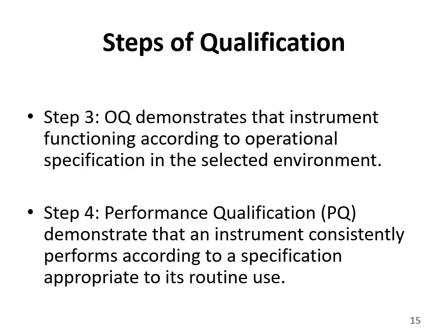Okay, and step 5, as I have told you earlier, I haven't given in the phases, as it's not part of your curriculum, but this is part of the qualification. So just for your knowledge, maintenance qualification, MQ, describes and documents any maintenance required on the equipment.